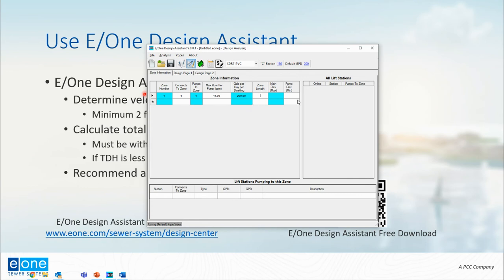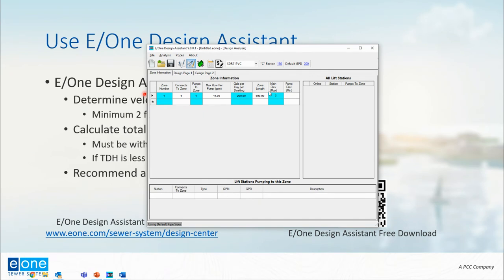Now zone length—this is where I start taking the information that was provided in that email. So I know my zone length is 500 feet, so I'm going to input 500 there. My maximum main elevation is the top of that hill, and just for simplicity's sake I'm just going to put that the maximum main elevation is 25 feet. The pump elevation and the minimum pump elevation is going to be zero feet, and that's how I'm going to tell the software basically that there's a 25-foot elevation rise.